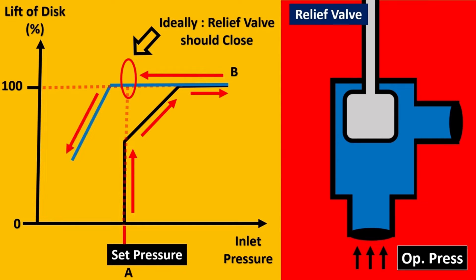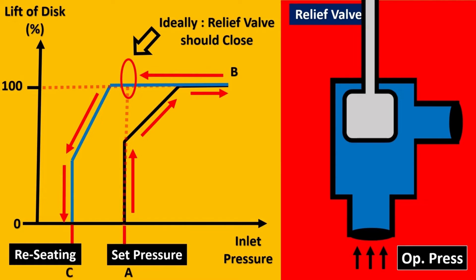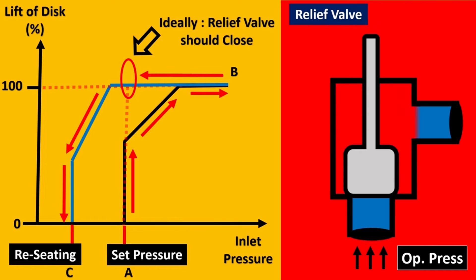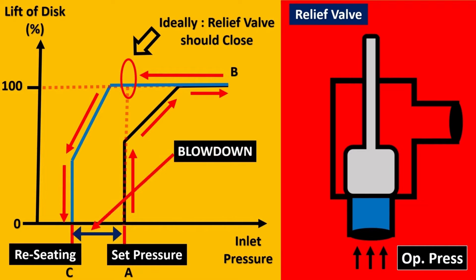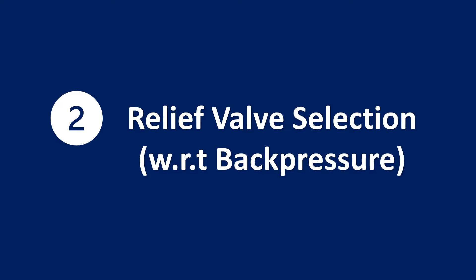Why does this happen? The pressure continues to drop even further, and only when it reaches the reseating pressure — let's call it point C — will the relief valve actually close and stop relieving fluid. This difference between the reseating pressure and the set pressure is what is called blowdown.